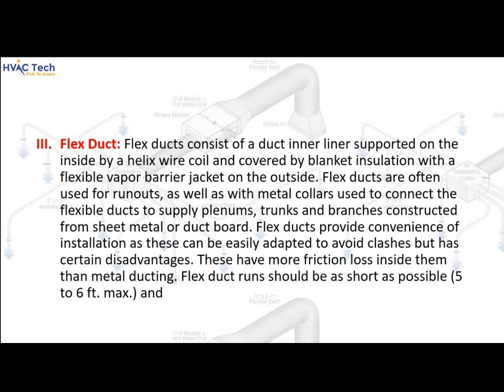Flex ducts consist of a duct inner liner supported on the inside by a helix wire coil, covered by blanket insulation with a flexible vapor barrier jacket on the outside. Flex ducts are often used for runouts, as well as with metal collars to connect flexible ducts to supply plenums, trunks, and branches constructed from sheet metal or duct board. They provide convenience of installation as they can be easily adapted to avoid clashes, but have more friction loss inside them than metal ducting. Flex duct runs should be as short as possible — five to six feet maximum — and should be stretched as tight as possible.